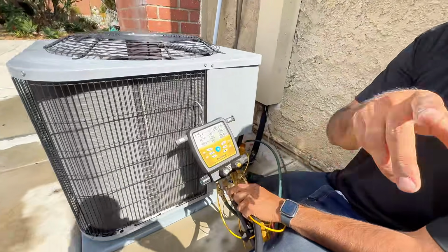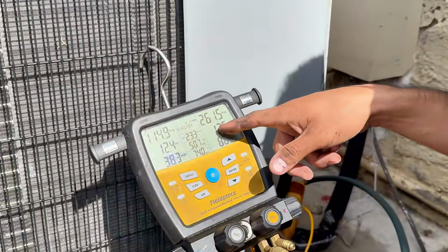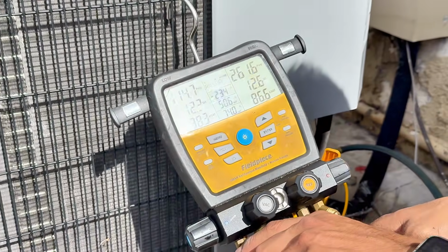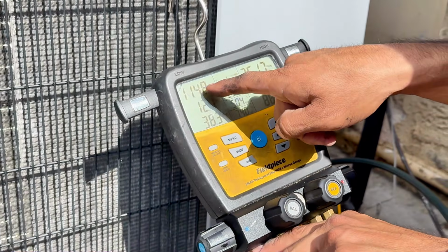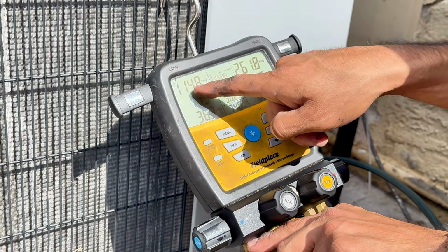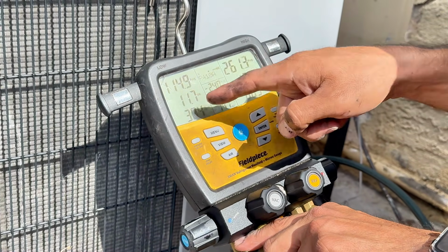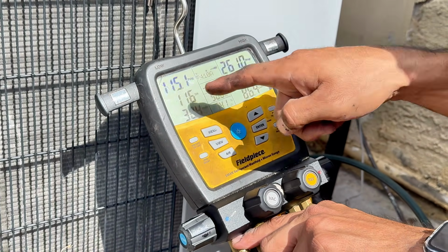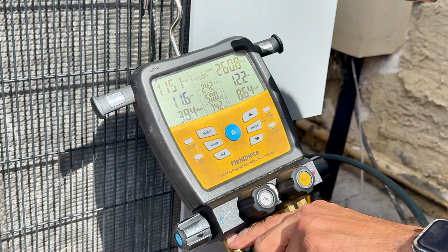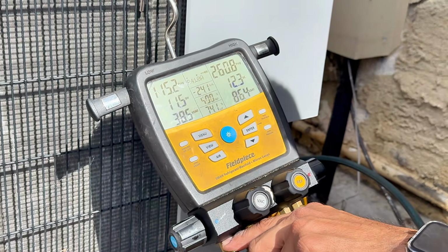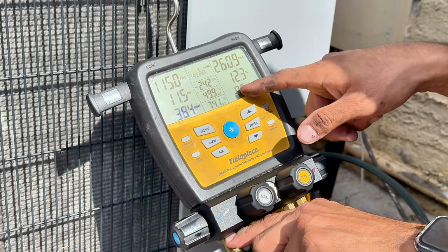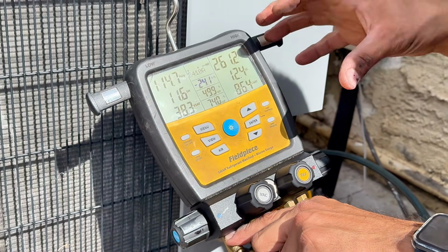Okay, let's see. Are you able to see pretty good right there? All the numbers? Okay. So it's a 410A system. My suction pressure is 114. When you convert that to temperature, we have a 38-degree evaporator temperature. My head pressure is 260. You convert it to temperature, and it's an 86-degree condensing temperature.